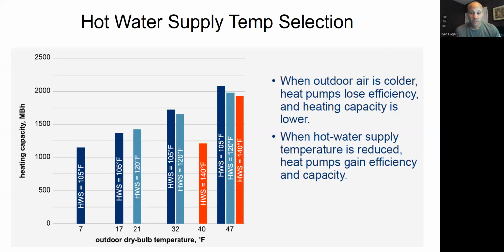In terms of the water temperature, kind of like what we talked about on the heating side for heat pump boilers, these heat recovery chillers and heat pump chillers have a similar scenario. Depending on the outdoor air temperature you need to operate at, you're going to be challenged to get certain water temperatures. So if it's only 0 or 7 degrees outside, it's really hard to make 140-degree water with some of these machines. I may only be able to make 105-degree water on some machines, right? That doesn't mean it's a bad idea. It just means somebody else has to help me heat it. So I might be taking that 105-degree heat from the chiller and using that to preheat my domestic water, which is coming in from the city at 50 or 55 or 60 degrees.